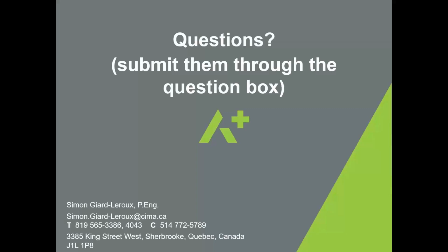So the Category 0 used to be 1.2 calories. Now any mention of Category 0 has been removed. But I believe, if I'm not mistaken, it is still present in the NFPA 70E. So these would be the two differences in my opinion.